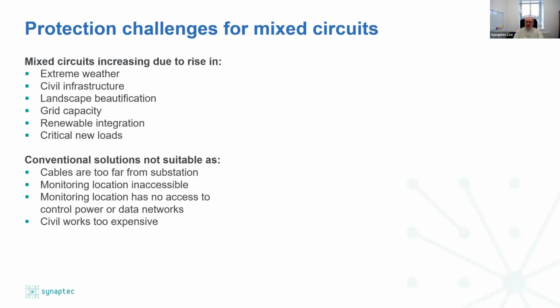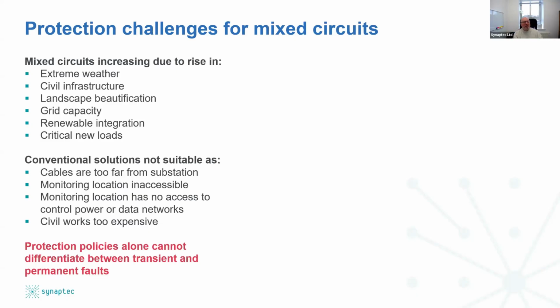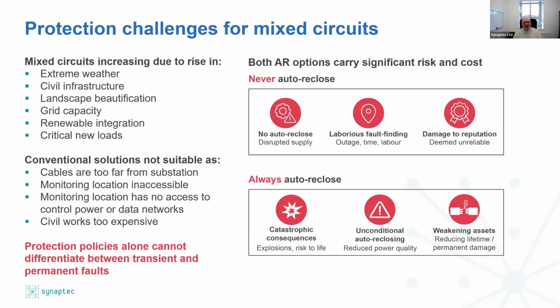If you think of Neil's presentation, what we're effectively saying is you've got information about assets inside the substation as if they were in the yard, but we're reaching out past the fence and going very far away to these remote and inaccessible locations to give you that instantaneous visibility and control of what's happening out there. So sometimes the location, like a transition point of an overhead line going to a cable section, it's simply too far away, or it's too inaccessible, or it would cost way too much money to build a substation and then the dedicated secure telecoms to knit the information back to the center to compare currents and understand where the fault is. So protection policies and protection budgets don't easily align on this one. And it's true to say that the policy itself doesn't completely work.